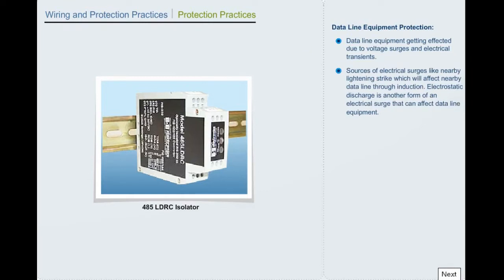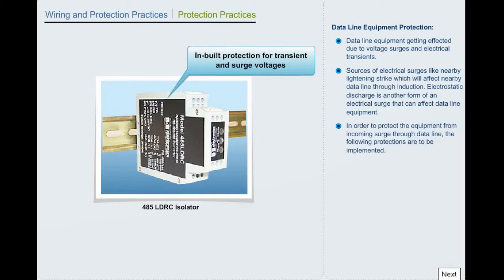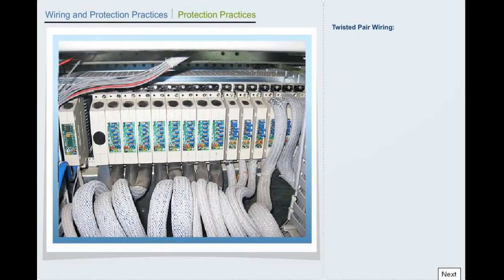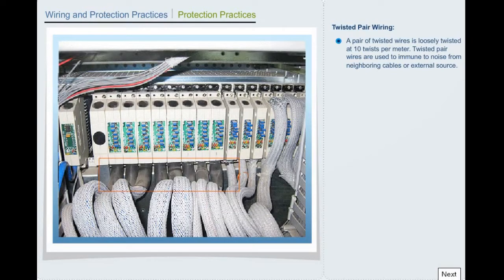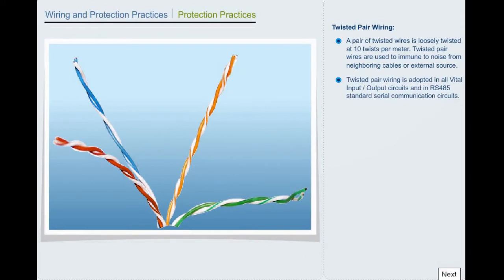Sources of electrical surges like nearby lightning strike, which will affect nearby data line through induction. Electrostatic discharge is another form of an electrical surge that can affect data line equipment. In order to protect the equipment from incoming surge through data line, the following protections are to be implemented. Twisted pair wiring. A pair of twisted wires is loosely twisted at 10 twists per meter. Twisted pair wires are used to be immune to noise from neighboring cables or external source. Twisted pair wiring is adopted in all vital input and vital output circuits and in RS-485 standard serial communication circuits.